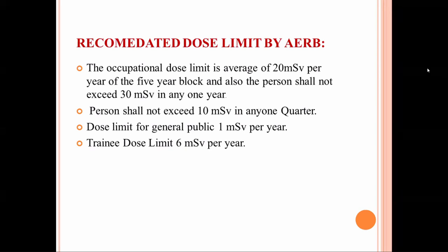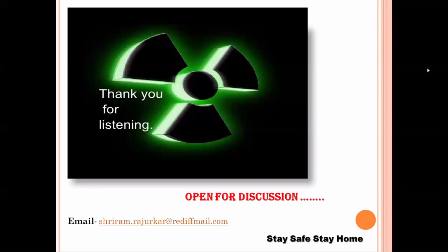A person shall not exceed 10 mSv in any one quarter; if a dose of 12 mSv is received in one quarter, it constitutes overexposure. The dose limit for the general public is 1 mSv per year. Trainees and interns have a dose limit of 6 mSv per year. There is no dose limit for patients receiving radiation treatment, as they receive benefits from radiation. Occupational workers above age 18 have a limit of 20 mSv per year.